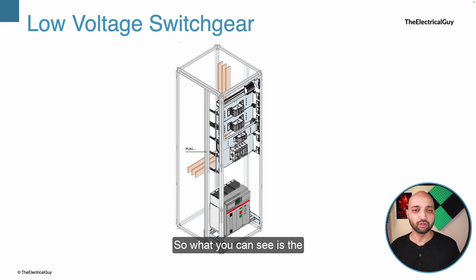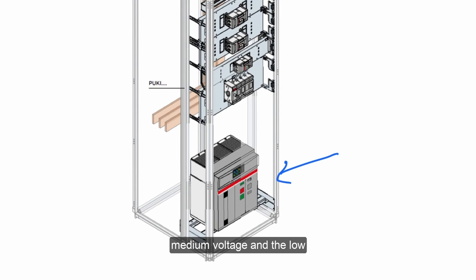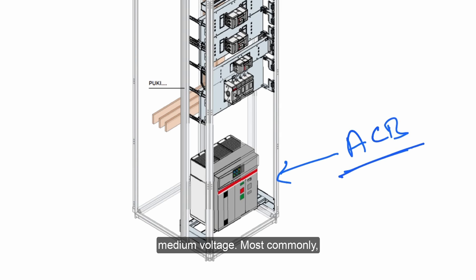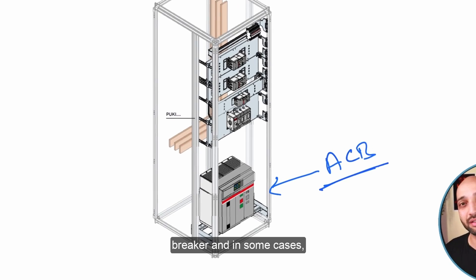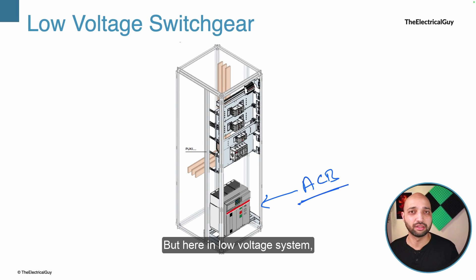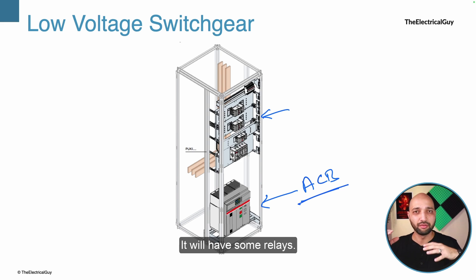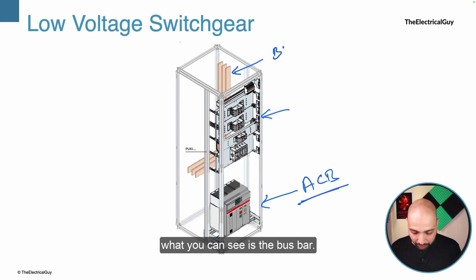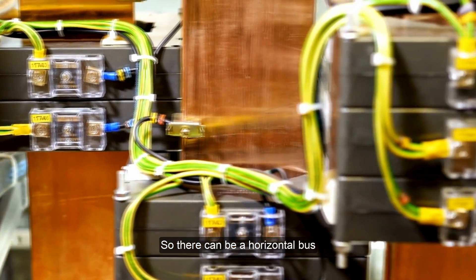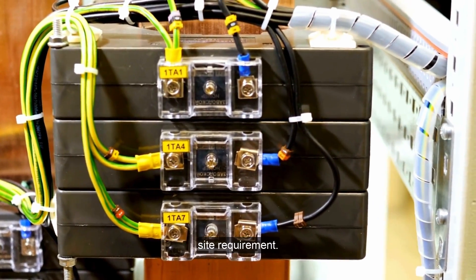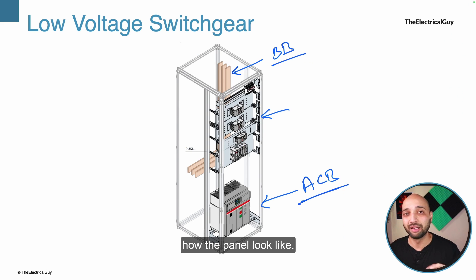Here is an example of a low voltage switchgear panel. At the bottom you can see a circuit breaker. The key difference from medium voltage switchgear is that the circuit breaker used here is an air circuit breaker (ACB). Medium voltage most commonly uses a vacuum circuit breaker, and in some cases an SF6 circuit breaker. But in low voltage systems, the majority of breakers are air circuit breakers. You can also see control circuitry with relays, meters, and MCBs, and at the back in brown you can see the bus bar. Bus bars are really important; there can be horizontal or vertical bus bars depending on site requirements.